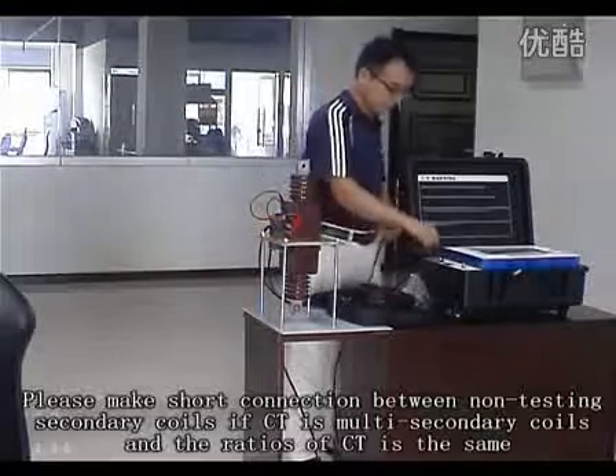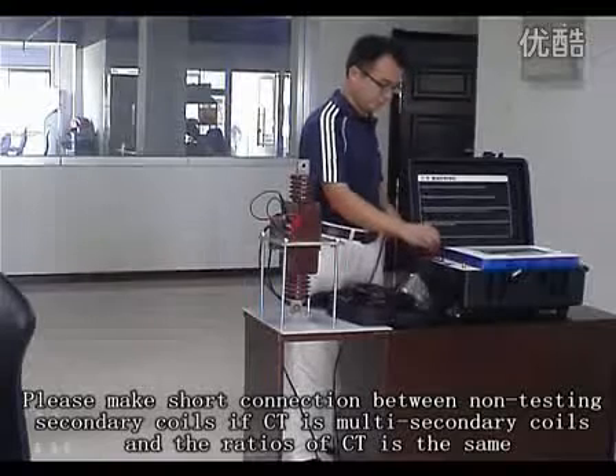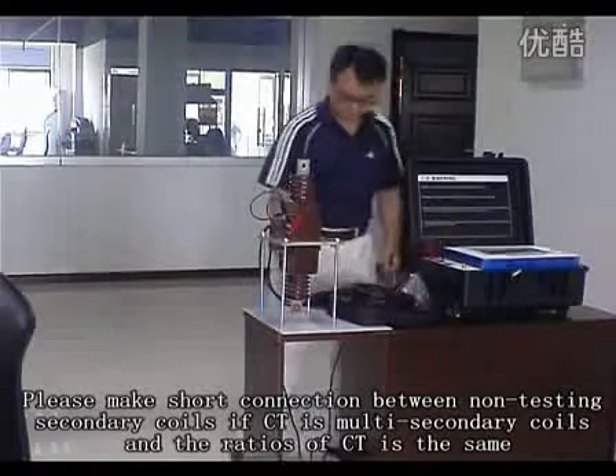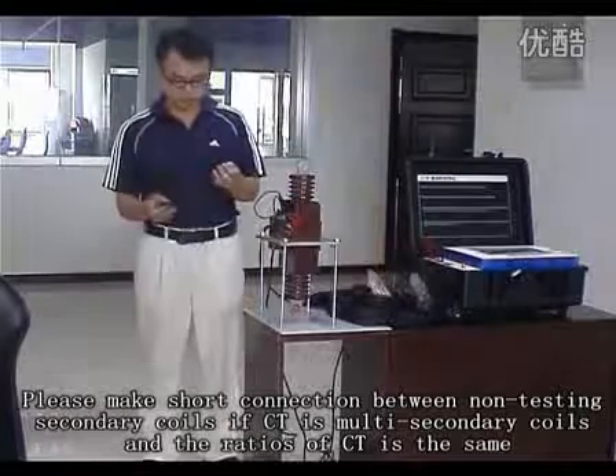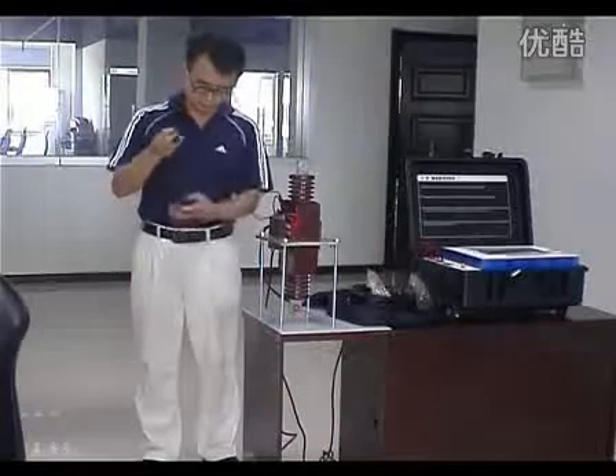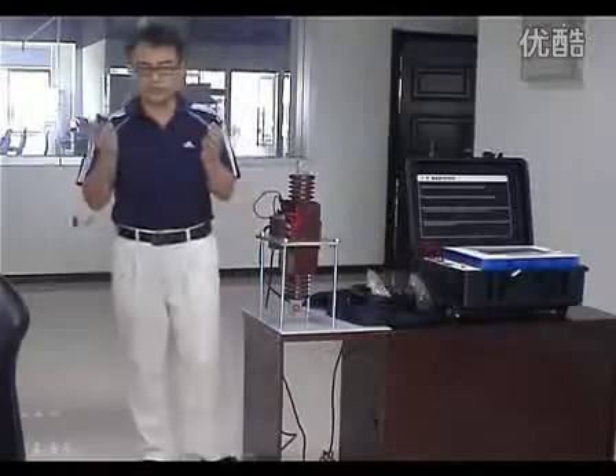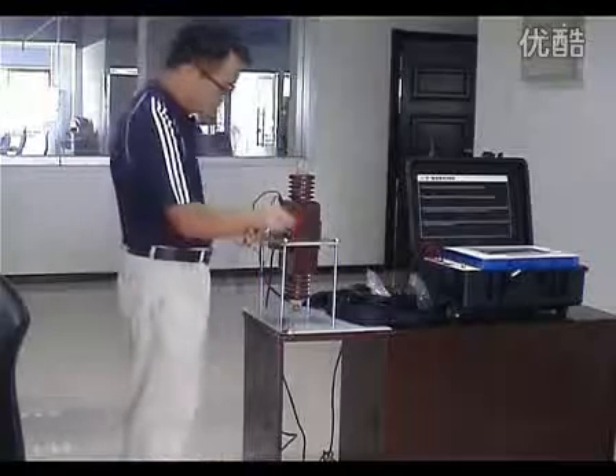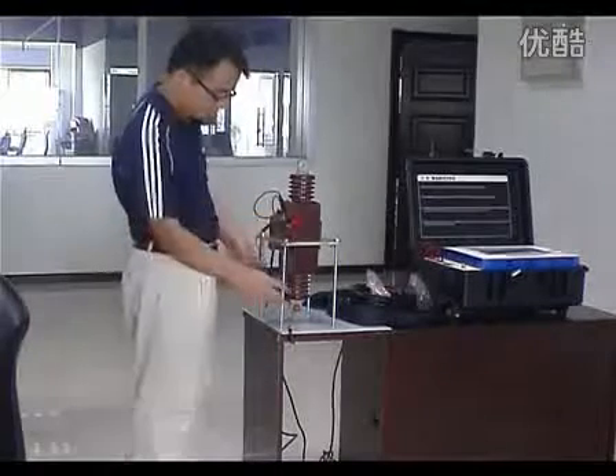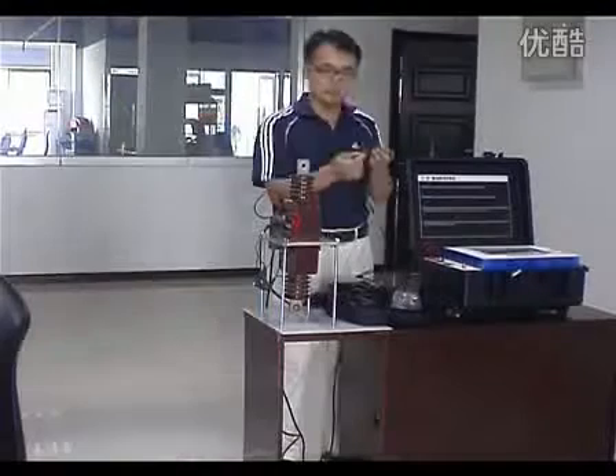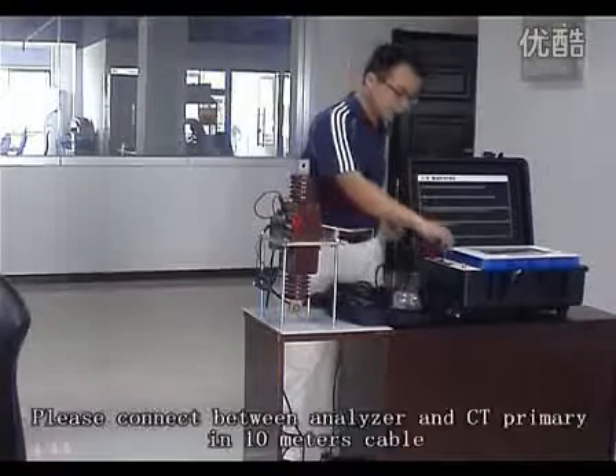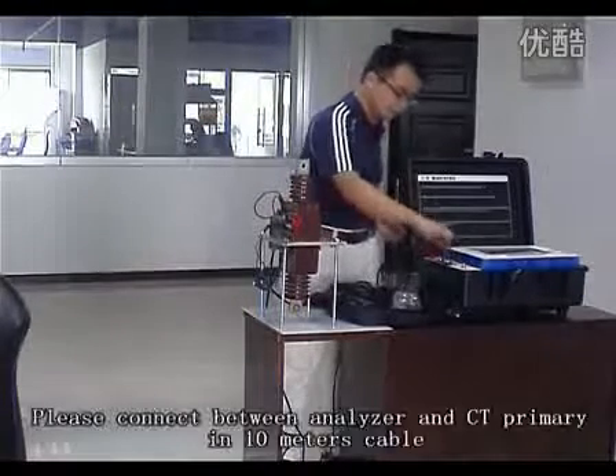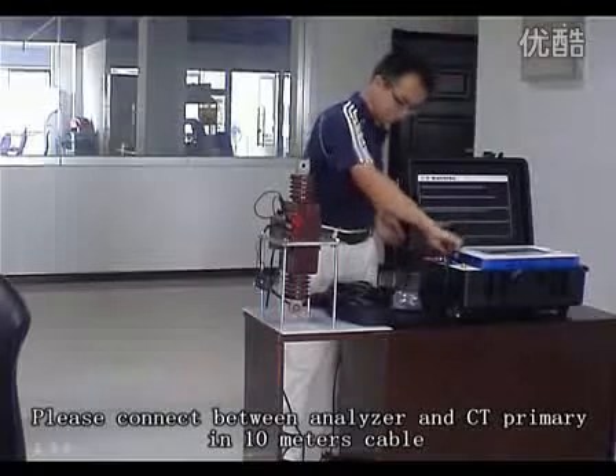Please make a short connection between non-testing secondary coils if the CT has multiple secondary coils and the ratios of the CT are the same. Please connect between the analyzer and the CT primary with the 10 meter cable.